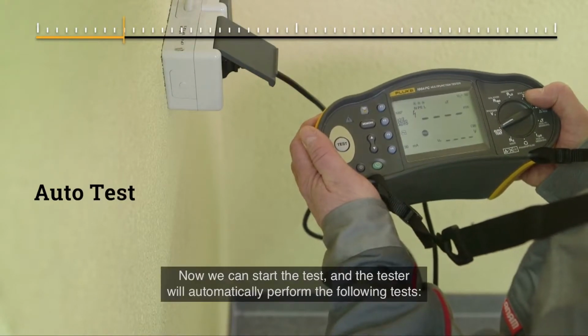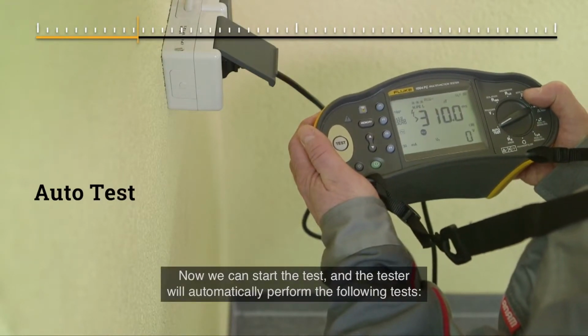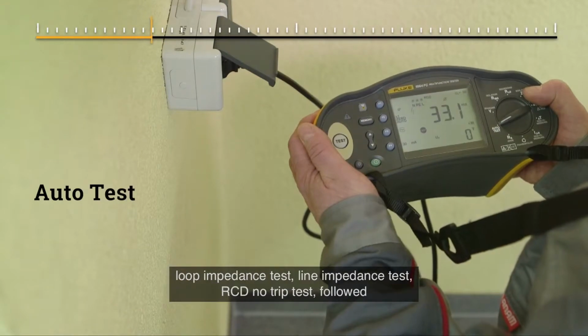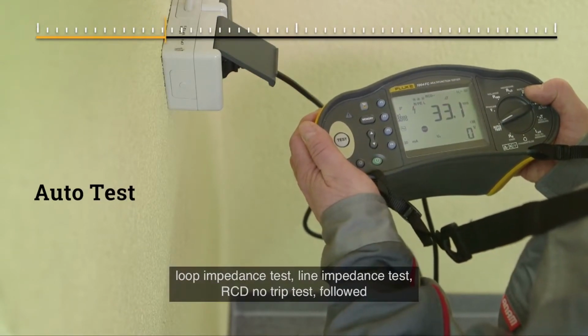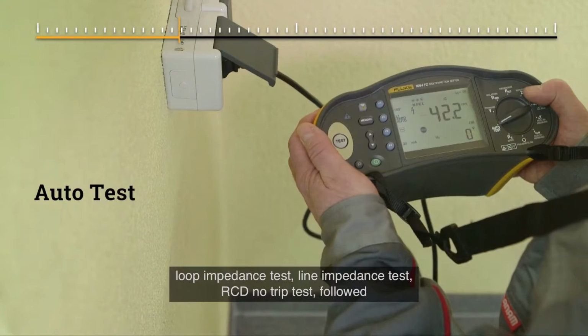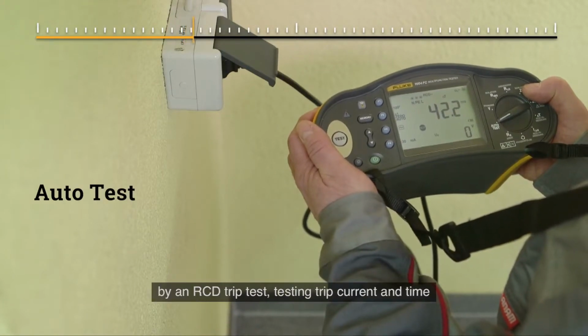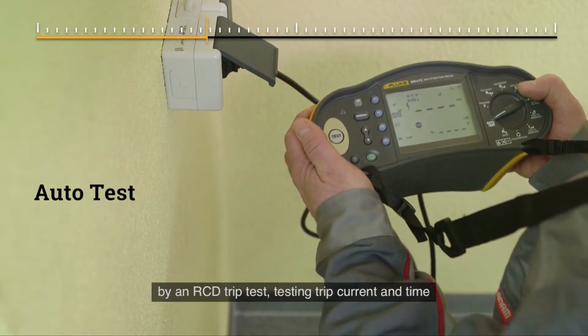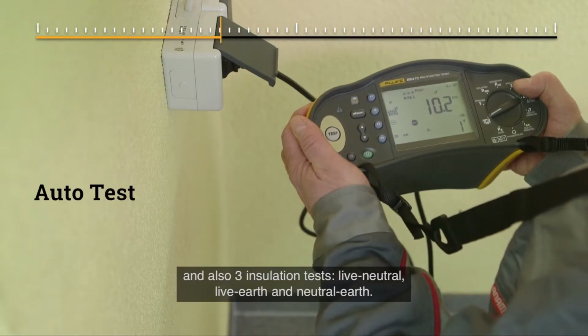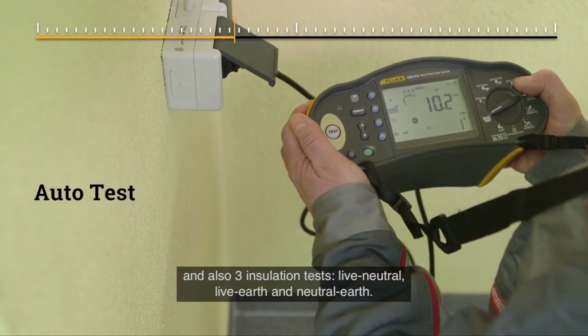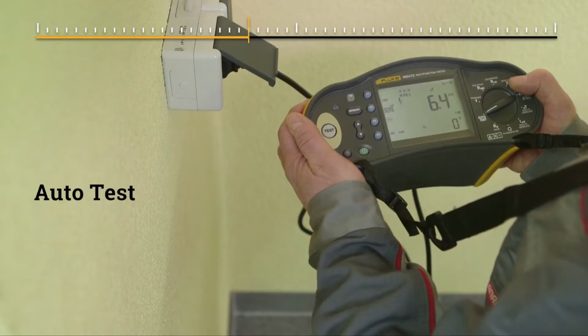Now we can start the test, and the tester will automatically perform the following tests: loop impedance test, line impedance test, RCD no-trip test, followed by an RCD trip test, testing trip current and time, and also 3 insulation tests: live neutral, live earth, and neutral earth.